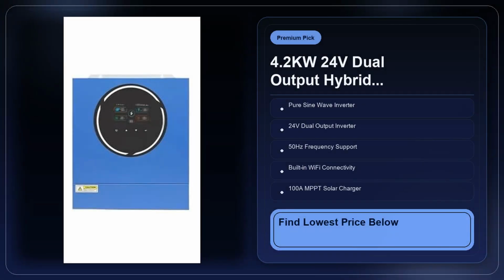but it's there. The built-in BMS communication, RS485, is a nice feature for those who already have a battery management system that supports it. It lets the inverter pull real-time health data from the battery, such as temperature and cell balance, and adjust its charging algorithm accordingly. For a lithium pack, that can prolong cycle life by a few percent. If you're using lead-acid batteries, the RS485 port will sit idle, so you won't get that extra intelligence. In short, the BMS link is a win for the technically inclined, but a neutral point for the average homeowner.